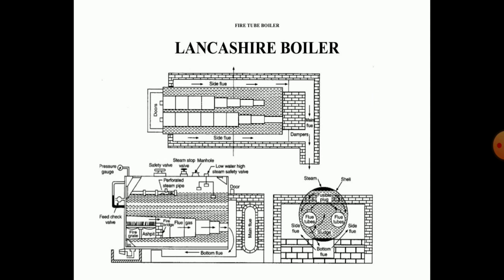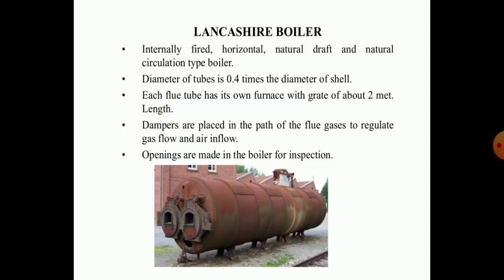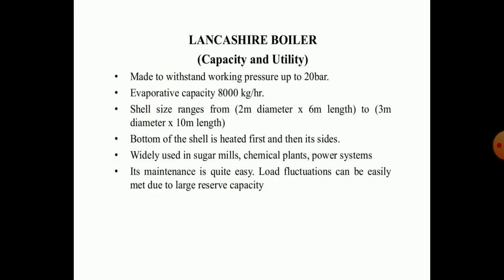You can see the Lancashire boiler and its various parts on screen. The Lancashire boiler is an internally fired, horizontally oriented, natural circulation type boiler. The diameter of the tubes is generally 0.4 times the diameter of the shell, and each flue tube has its own furnace with a grate of about 2 meters in length. Dampers are placed in the path of the flue gases to regulate gas flow, and openings are made into the boiler for inspection purposes. The Lancashire boiler is designed to withstand a working pressure of 20 bar, with an evaporative capacity of about 8000 kg per hour.